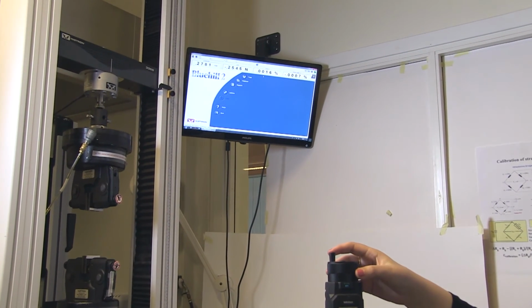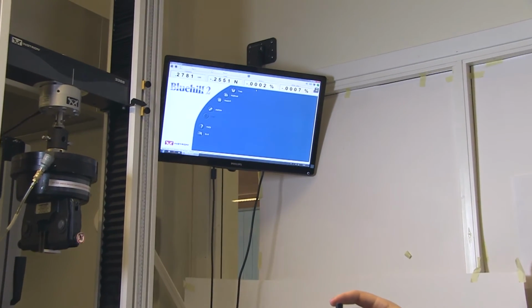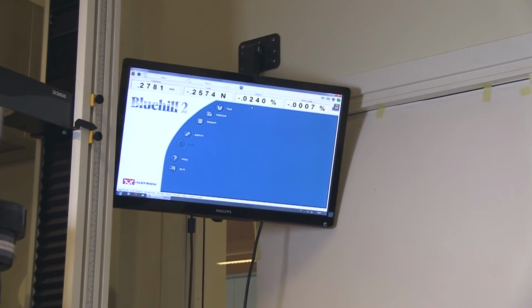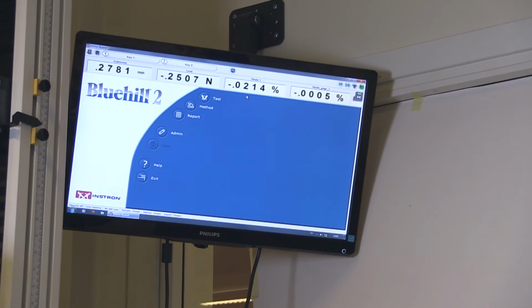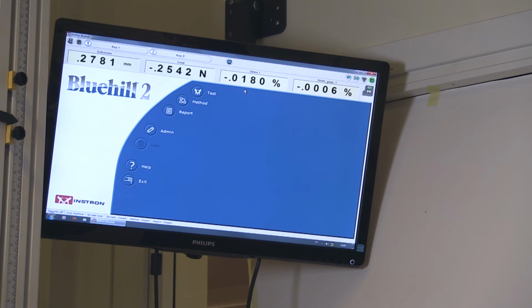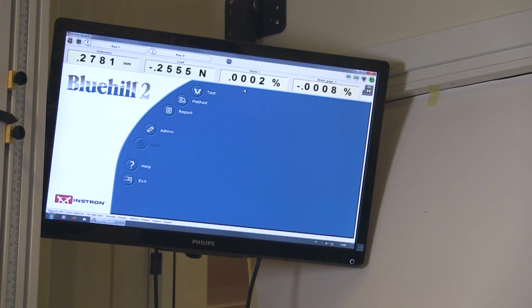And then when I exceed the value, I have to go back, and then I start again. Because of the thread here, we cannot go back and forward from the 0 value. When we exceed it, we have to start from the beginning, and we go slowly until we get 0 value on the screen for the displacement.